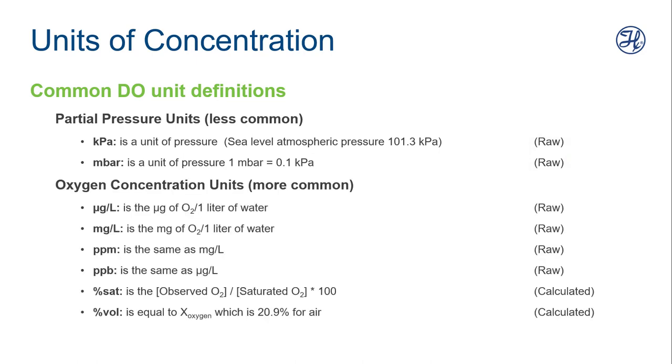But most people use oxygen concentration units, so they're a little bit more common. Here are some that you might be familiar with. We have micrograms or milligrams per liter, which are related to the dissolved oxygen in water, in one liter of water. Those are equivalent to PPM and PPB, and these are actually raw measurements. But then we have percent saturation, which is very commonly used, and percent by volume. These are calculated units, so they factor in the value of atmospheric pressure that's stored in the sensor.